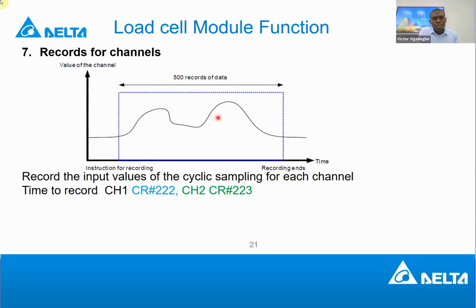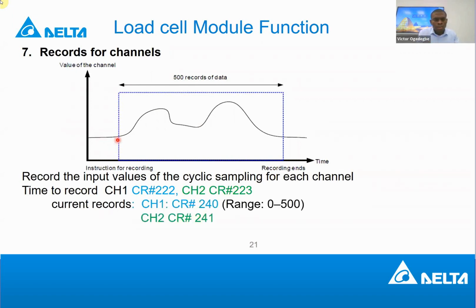So for this, you can set the time of record. The time of record is from 1 millisecond to a maximum of 1 second, and you specify the time here. This is for channel 1. You specify at what time you want to record the data, that you want to keep in the record register. The default is 1 millisecond, if I'm not mistaken, but the maximum is 1 second.